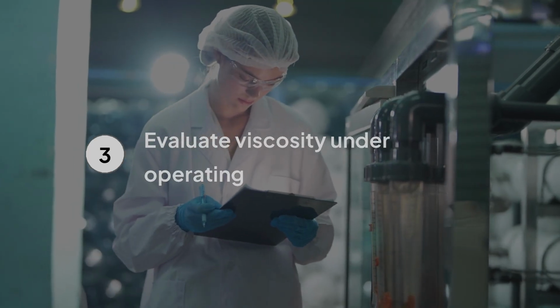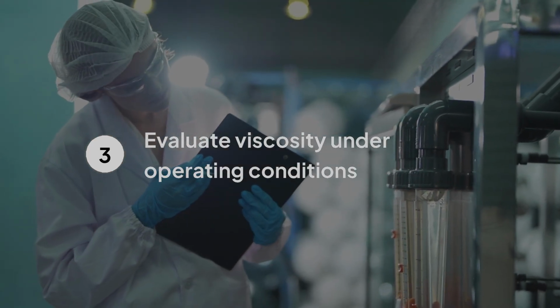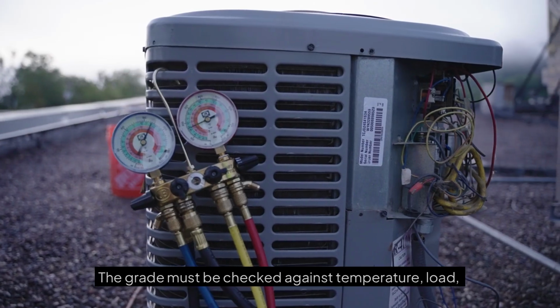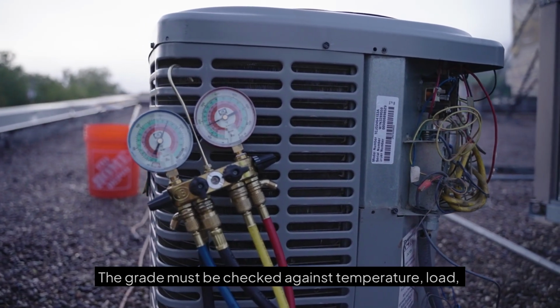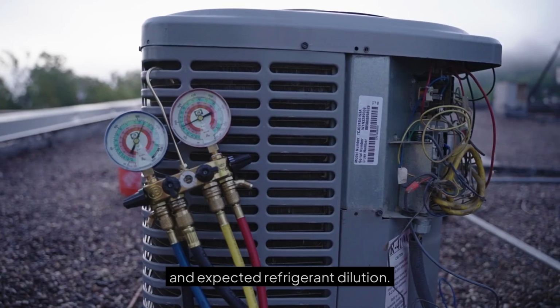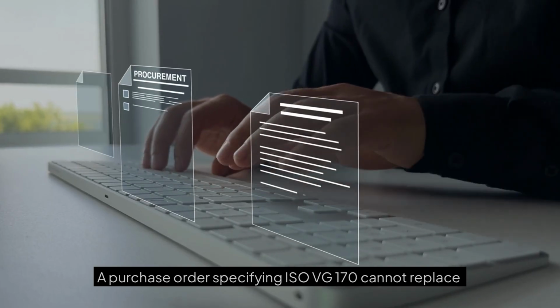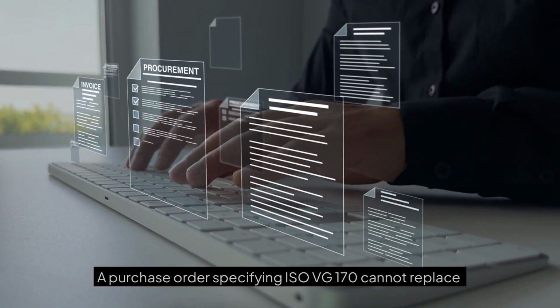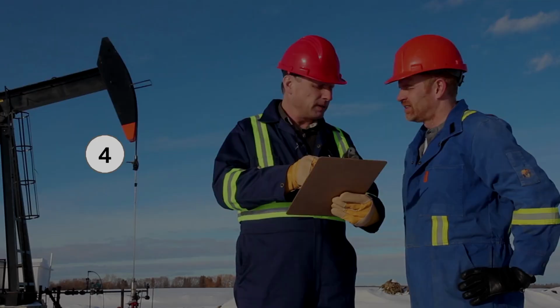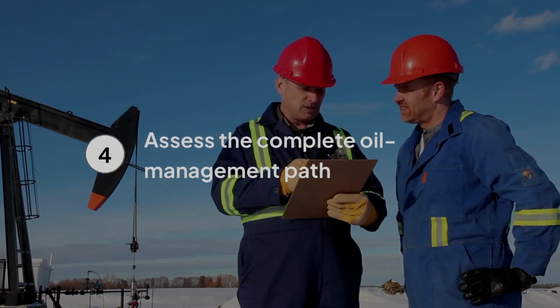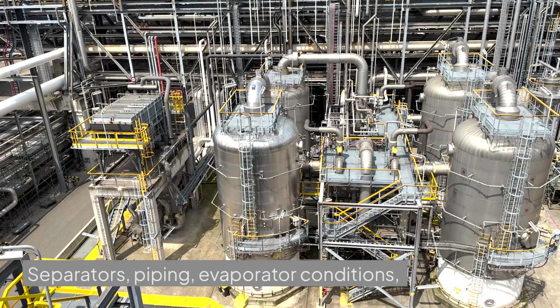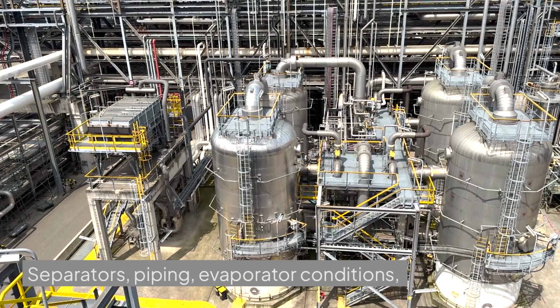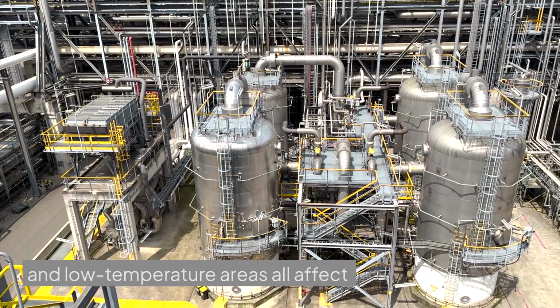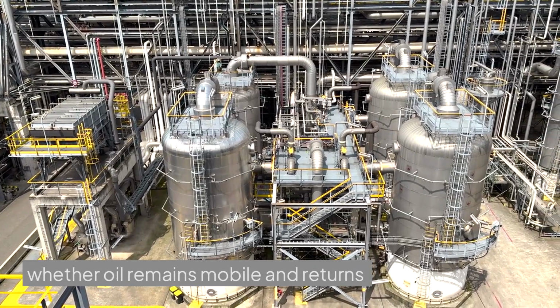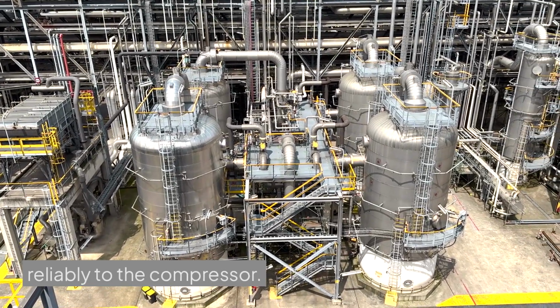Third, evaluate viscosity under operating conditions. The grade must be checked against temperature, load, and expected refrigerant dilution. A purchase order specifying ISO VG 170 cannot replace that engineering review. Fourth, assess the complete oil management path. Separators, piping, evaporator conditions, and low-temperature areas all affect whether oil remains mobile and returns reliably to the compressor.